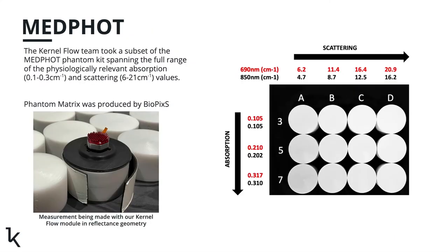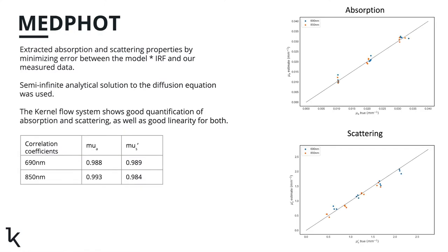Having completed the more fundamental device characterization, we now move on to evaluating how accurately our system can extract optical properties from known phantoms according to the MEDPHOT protocol. We selected this range of optical properties for our phantoms in order to match the expected biologically relevant range of values. For these measurements, we used an array of 12 phantoms with known optical properties that we acquired from Biomimic. Each phantom is 5 centimeters tall and 10 centimeters in diameter. For the optical properties of these phantoms, this size is sufficient to make a semi-infinite approximation reasonable, and we use a semi-infinite diffusion model when extracting optical properties from the measured histograms. Here we show the results of using our measurements along with the semi-infinite model to estimate the optical properties of each phantom in the set. What we find is that we have good linearity for each step change in absorption or scattering for both wavelengths. Our accuracy for absorption is better than that for scattering, which is in agreement with similar findings by other TD-NIRS systems.